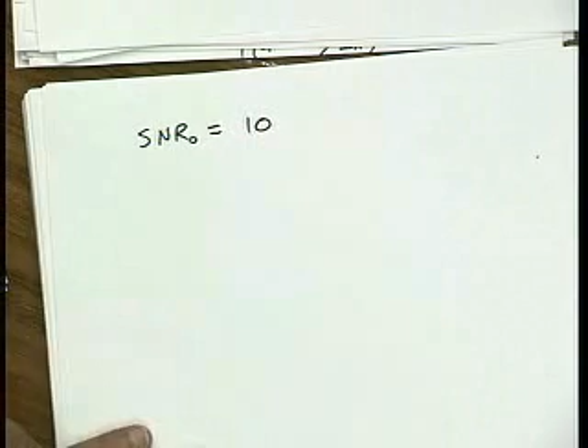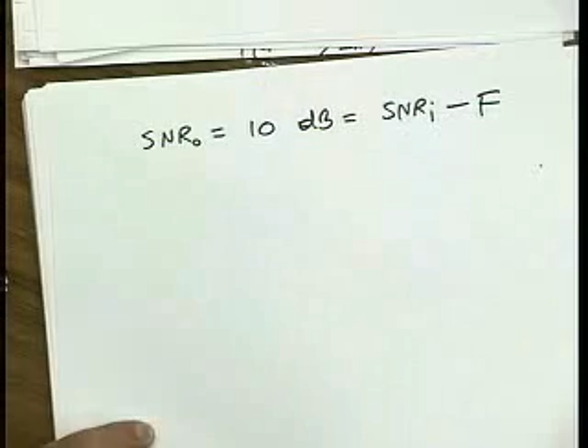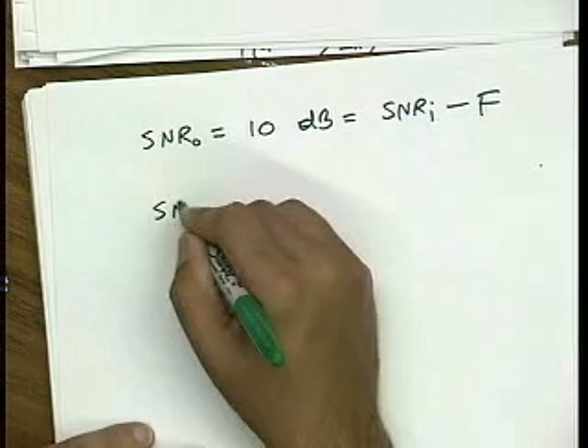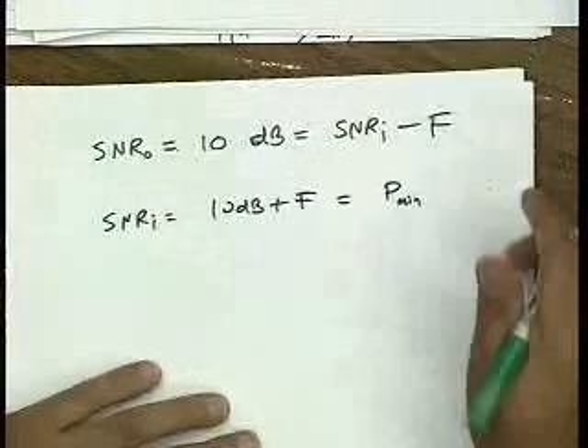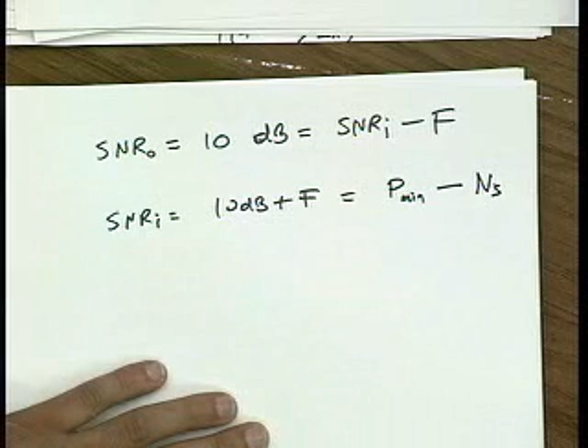By definition, we want the signal-to-noise ratio at the output to be 10 dB, or a factor of 10, and that's the SNR at the input minus F, right? Because the system always degrades the noise figure. So all we have to do here is solve for the SNR at the input, which is 10 dB plus F, and we set the SNR at the input equal to P min, the minimum signal that we can detect, minus the noise at the source. And so P min is 10 dB plus F plus the noise of the source.